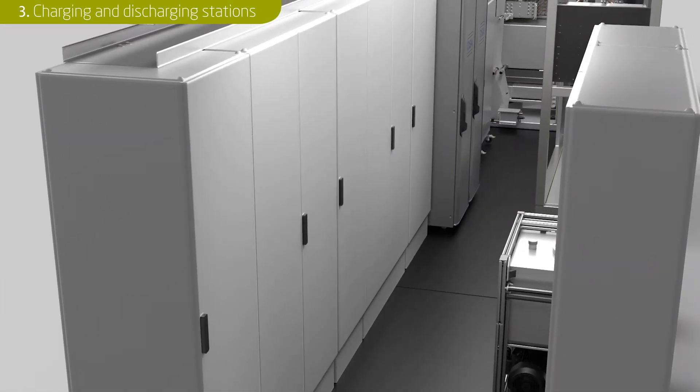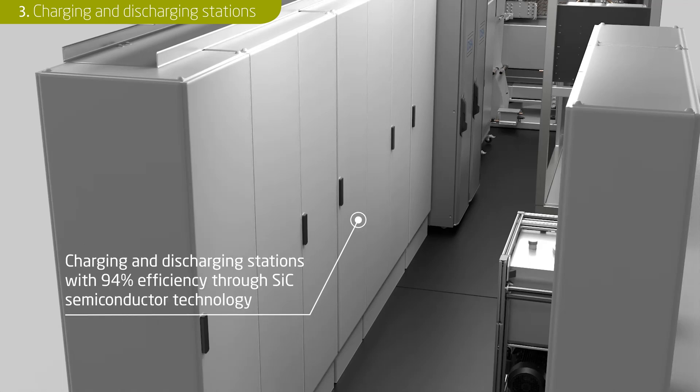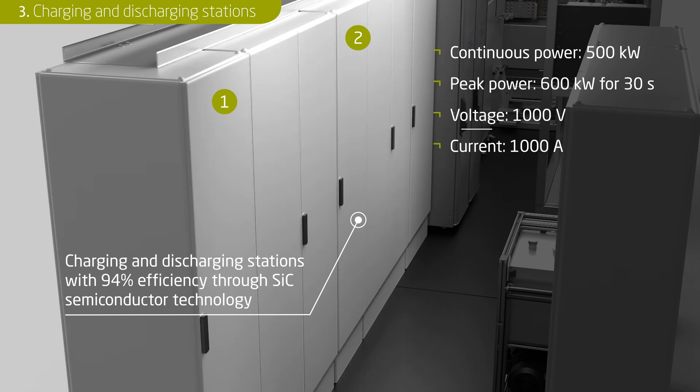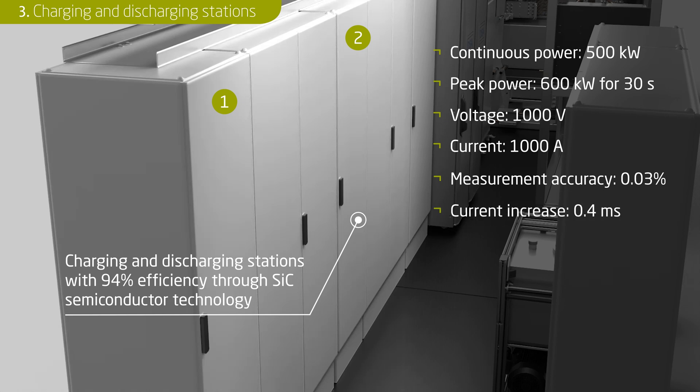The heart of the mobile climate test laboratory are the compactly built charging and discharging stations. An efficiency of 94 percent is achieved thanks to the implemented silicon carbide semiconductor technology. Each charging and discharging station offers an output of 250 kilowatt. Up to 500 kilowatt of electrical power is available when up to two of these units are connected in parallel. A peak power of 600 kilowatt can also be achieved for 30 seconds. 1000 volts of output voltage and 1000 ampere of current are used for a wide range of battery tests. The control of the charging and discharging stations is highly precise with a measurement accuracy of 0.03 percent and allows current jumps in 0.4 milliseconds.